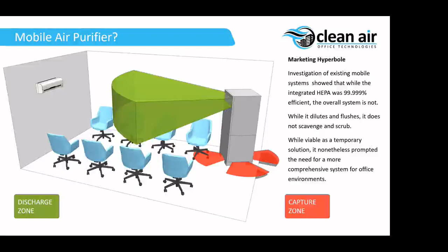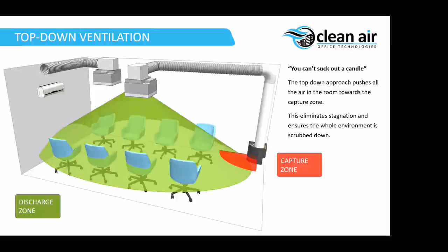We just bought another dimension. Yeah, exactly. So we quickly realised that it wasn't just a case of fans and filters. It was about how we distribute the air, exactly what we find from designing clean rooms. So the solution we eventually developed involves a high-level HEPA fan filter unit with a swirl diffuser. This is technology we brought over from the clean room industry, and it will basically sweep the entire room with a very broad cone of air at relatively high velocity, keep the particles buoyant, and sweep them all towards an extract point at low level. And this was the other key element for us, that we needed high-level supply, low-level extract. We experimented with high-level extract, but what we found was that as soon as we switched on any incumbent air conditioning systems, it completely disrupted that process, and we just weren't getting the capture rate that we needed.